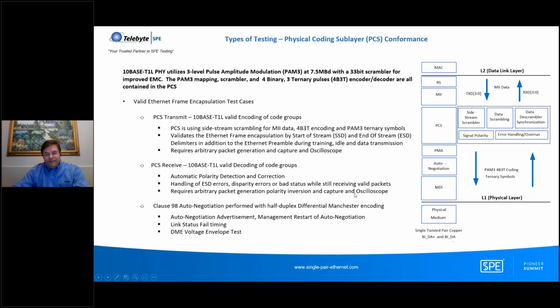Then the third type of test here is testing the auto negotiation layer of the physical layer, and that would be with half duplex differential Manchester encoding. When we go into auto negotiation, there are two devices on the link, right? It's a point-to-point connection. They have to advertise their capabilities, and then they have to negotiate common capabilities between them. So we test the auto negotiation features of restart of negotiation, test link status, fail. If we do fail an auto negotiation, we have to wait so long and then retry again. We also look at the differential Manchester encoding voltage amplitudes. So this is all part of the physical layer testing here.